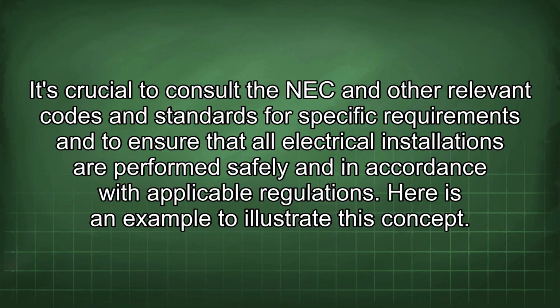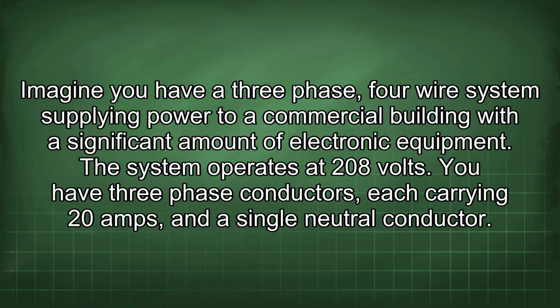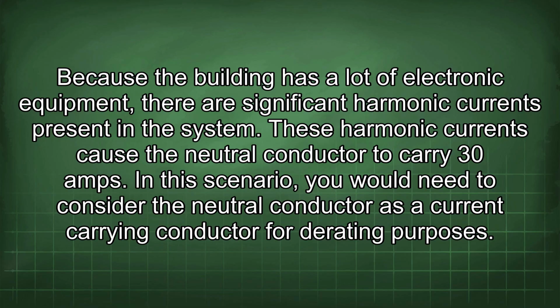Here is an example to illustrate this concept. Imagine you have a three-phase, four-wire system supplying power to a commercial building with a significant amount of electronic equipment. The system operates at 208 volts. You have three-phase conductors, each carrying 20 amps, and a single neutral conductor. Because the building has a lot of electronic equipment, there are significant harmonic currents present in the system. These harmonic currents cause the neutral conductor to carry 30 amps. In this scenario, you would need to consider the neutral conductor as a current-carrying conductor for derating purposes.